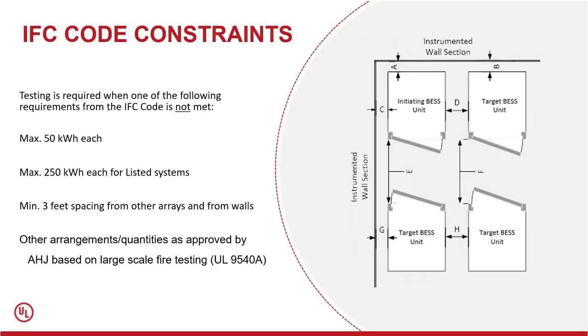This was the initial language within our fire code at the time. It said we were going to maximize the battery unit to 50 kilowatt hours, and a system was going to be limited to 250 kilowatt hours. We were also going to require a minimum of 3-foot separation from the unit, and the unit from the wall.